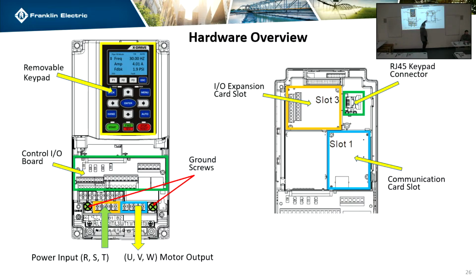Slot 3, right here, we have I/O expansion cards, and we also have, I think, a 120 volt power supply card. That would go up here. I have to double check the ones that go up here. And then down here, this is where the Bluetooth card would be. Slot 1 is for the Bluetooth card. It's also for the Ethernet card, so it's one or the other.